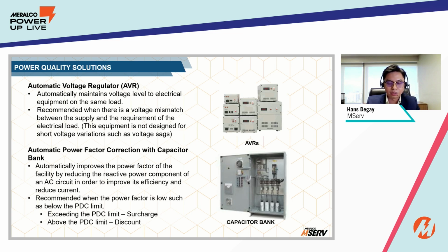The next item is the capacitor bank, more commonly known to improve the power factor of the facility. Not only is it possible to avoid surcharge penalties and get a discount instead, the overall kVA load of the facility is reduced. This means that the current passing to the cables and upstream of the capacitors is lower, with less stress on cables, transformers, etc. But it should also be noted that capacitor banks can create resonance. That's why part of the solution is harmonic filters, to avoid resonance and further problems with your power quality. Thorough study should be done when determining which power quality equipment to be used.